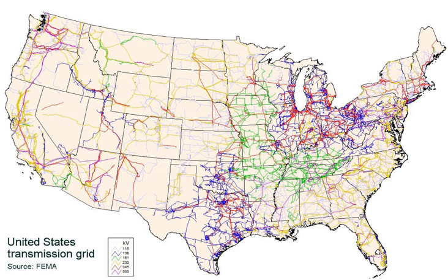If the entire grid tends to be overloaded, the grid frequency and hence actual speed of generators will decrease. All units will see an increase in the speed error, and so increase fuel flow to their prime movers and power output. In this way, droop speed control mode also helps to hold a stable grid frequency. The amount of power produced is strictly proportional to the error between the actual turbine speed and speed reference. It can be mathematically shown that if all machines synchronized to a system have the same droop speed control, they will share load proportionate to the machine ratings.